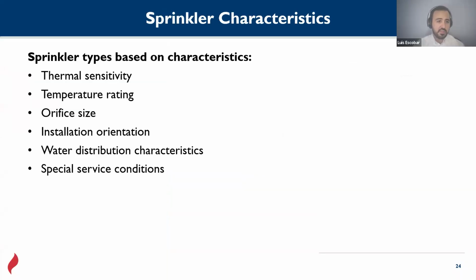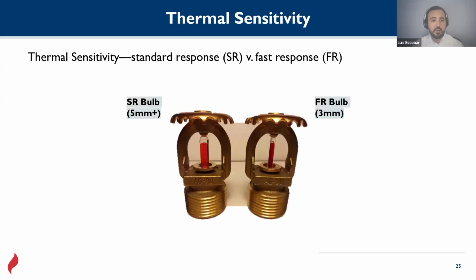Sprinkler types based on characteristics: thermal sensitivity, temperature rating, orifice size, installation orientation, water distribution characteristics, special service conditions. All these are going to be helpful so we can design our fire sprinkler system. There's not one more important than the other, but I would say all of them are very important. We need to take them all into account when it comes to designing a fire sprinkler system. The first one will be thermal sensitivity.